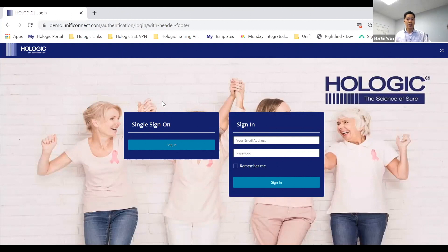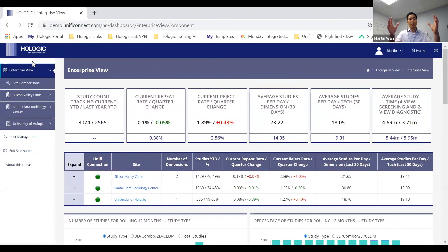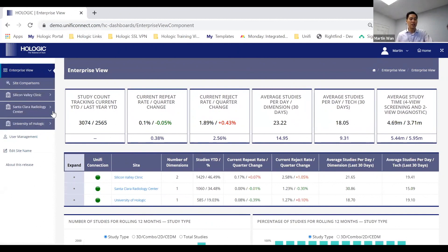When you dive into Unifi Analytics, it's a cloud-based platform — you can sign in from Google Chrome on a laptop, computer, or your phone. Once you sign in and click on Unifi Analytics, on the left is your navigation. We're starting at the top at the enterprise view, then the site comparisons view, and the individual sites: Silicon Valley Clinic, Santa Clara Radiology Center, University of Hologic. Within each individual site you can click in to see the devices and technologists.